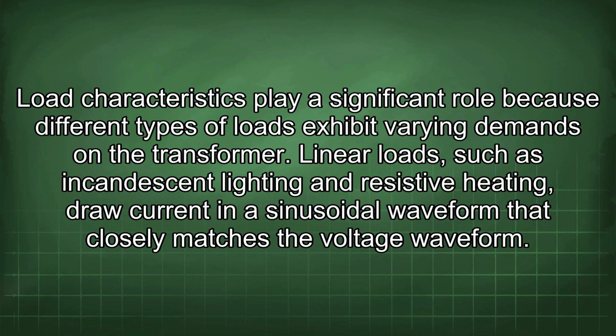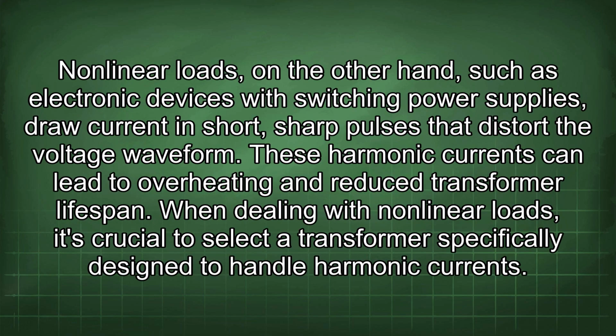Load characteristics play a significant role because different types of loads exhibit varying demands on the transformer. Linear loads, such as incandescent lighting and resistive heating, draw current in a sinusoidal waveform that closely matches the voltage waveform. Nonlinear loads, on the other hand, such as electronic devices with switching power supplies, draw current in short, sharp pulses that distort the voltage waveform. These harmonic currents can lead to overheating and reduce transformer lifespan.